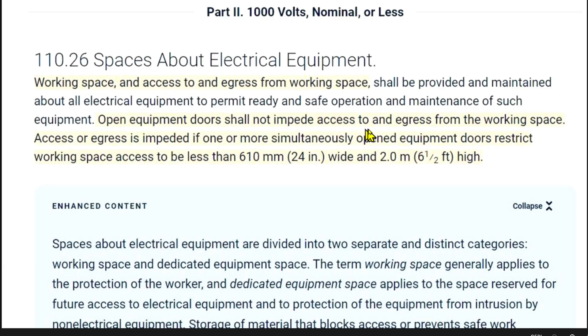Open equipment doors shall not impede access to and egress from the working space. Access or egress is impeded if one or more simultaneously open equipment doors restrict working space access to be less than 610 millimeters, that's 24 inches wide, and 2 meters, at 6 and a half feet high.